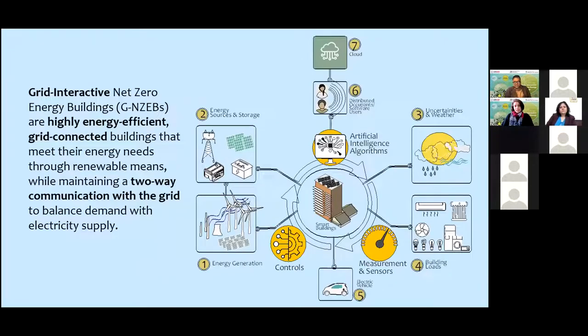So in a nutshell, grid interactive net zero energy buildings are highly efficient, grid connected buildings that meet the energy demand through renewable means while maintaining a two-way communication with the grid to balance demand and electricity supply. It has all these elements that you see: measurement systems, sensors, AI, controls that take into account uncertainties and weather patterns, managing building loads, generation, storage, even newer loads that are getting added into our network, like the EVs.